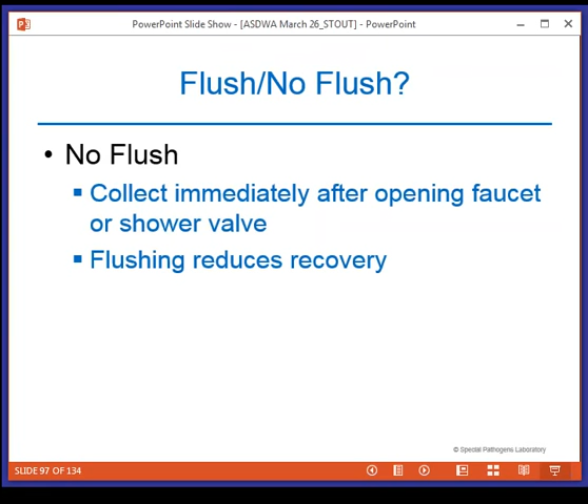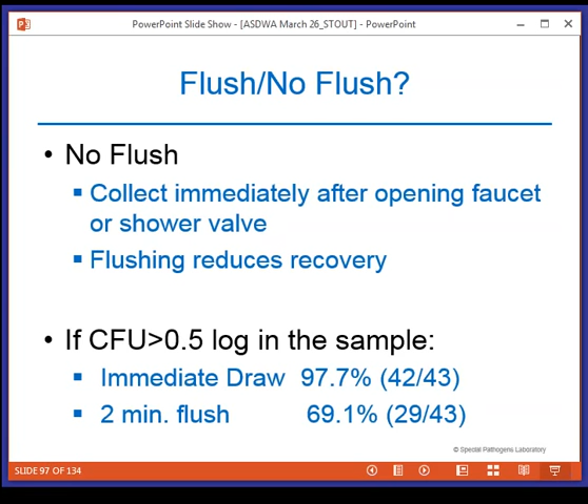So you collect an immediate sample after opening the fixture, without flushing, because flushing reduces recovery. In our case, it went from almost 98% of samples being positive down to less than 70%. So don't flush the outlet before collecting the sample for Legionella.